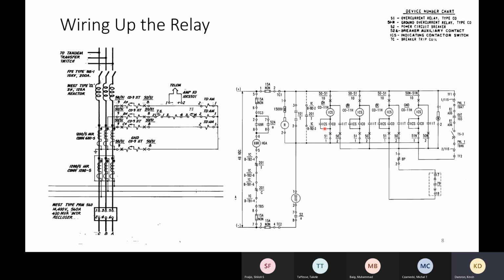If the relay operates, its contact closes, I energize the trip coil, but the breaker mechanically fails, then I can't clear the fault either. So there's the relay, the DC circuit, the breaker itself, and then the relay's basing its decision. In this case, since this is just an overcurrent relay, it's basing its decision off my CTs. So there's numerous things that are part of a protection system. And if you get into the bulk electric system, NERC actually has definitions. You Google NERC's glossary of terms and look up a protective system, they'll tell you everything that's incorporated.